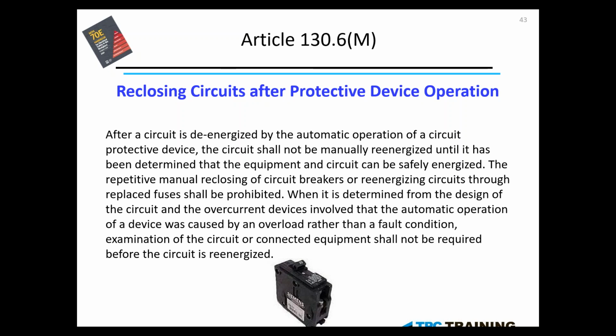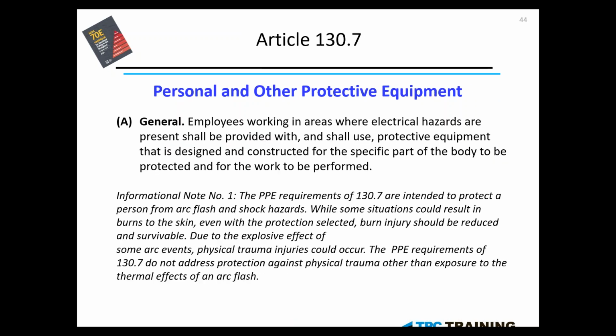So when a circuit breaker trips, we don't re-energize it until we can identify why it had tripped. Article 130.7 is your PPE article in the code book. We again will be covering that. Employees working in areas where electrical hazards are present shall be provided with the employer, and shall use the employee. Those are the two responsibilities in the general duty clause. Protective equipment that is designed and constructed for that specific body part to be protected and for the work to be performed. So this is that section in the code book that identifies when that PPE is required.